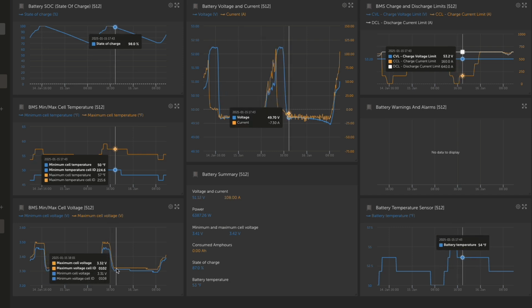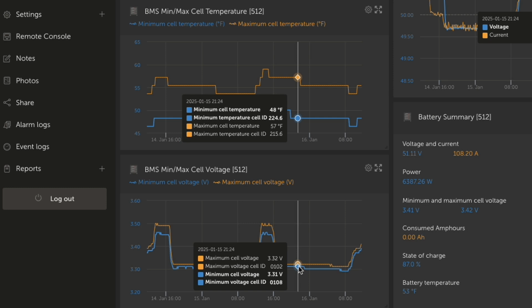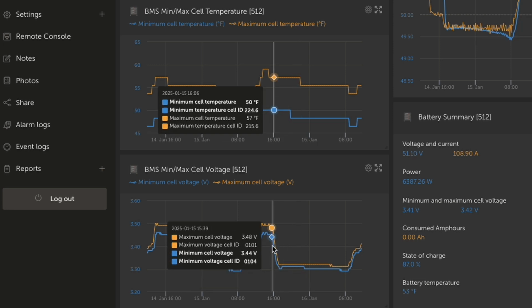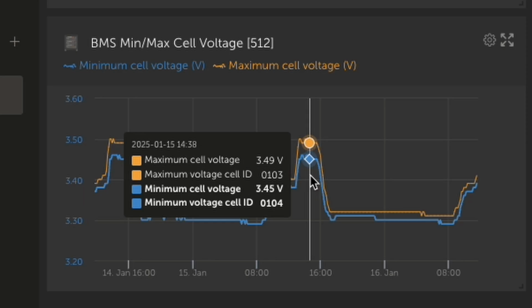You notice over here our minimum and maximum cell voltages. This is an indicator of overall battery bank balance. You'll see that it gets the most out of balance when it's at full. This is perhaps one cell that just takes a little bit more charge voltage than another. But overall, this system is always within a few hundredths. It's a very tightly focused, tight balance on the overall system here.